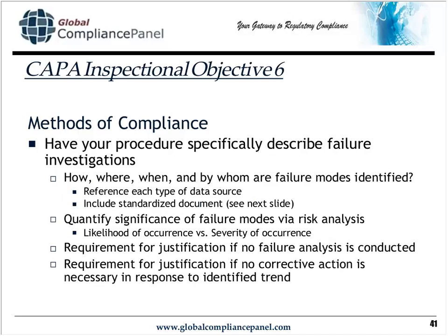The way to comply with this is, first off, to make sure your procedure describes your own failure investigations, the classic how, where, when, why, and who. Well, maybe not necessarily why in this case, but how are failure modes identified? By explicitly referencing each type of data source. Many firms I know have a standardized document, and I'll show you that momentarily, on which all of your failure investigations are documented. It works out really well because once the inspector has seen that document, he or she gets comfortable with it as the inspection progresses.